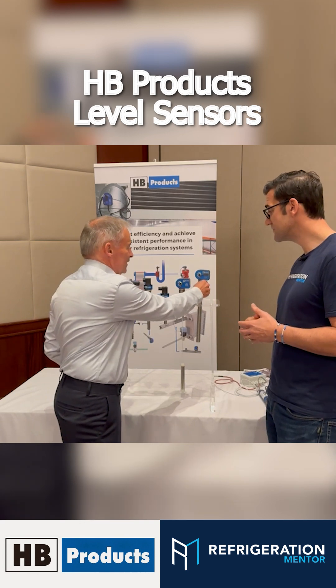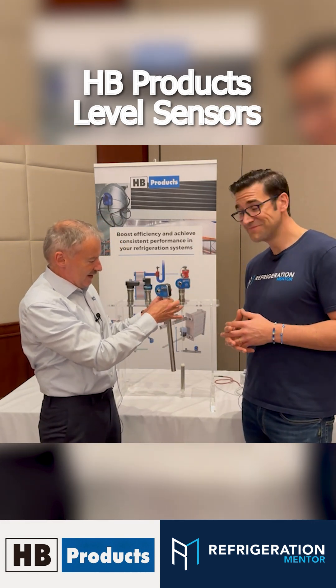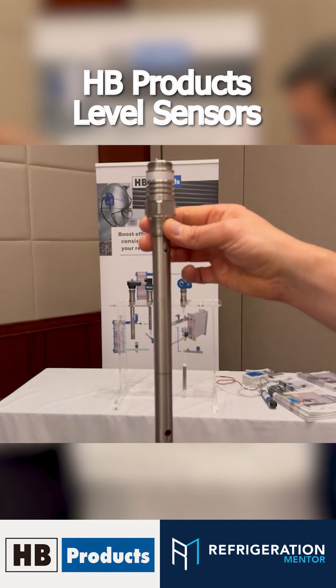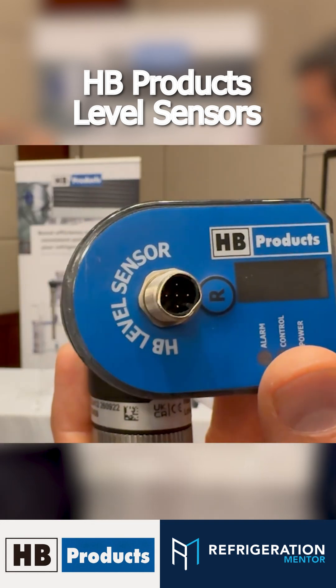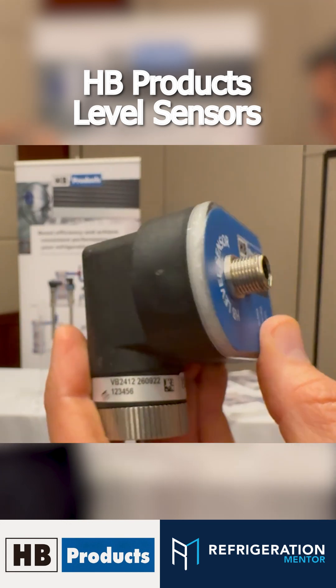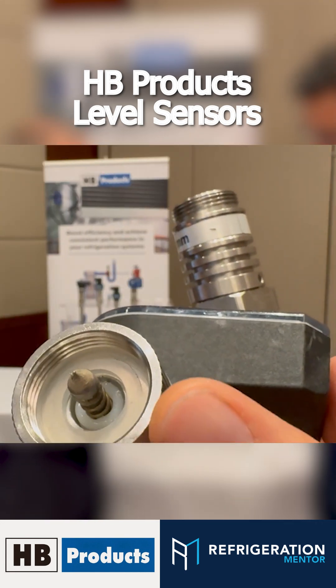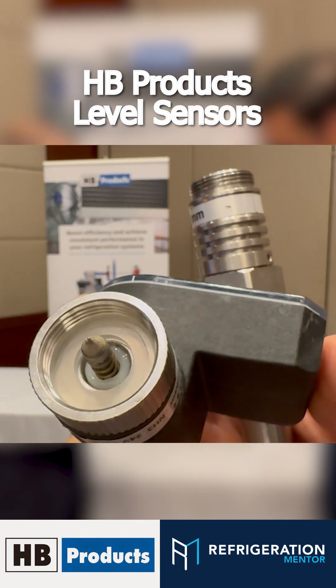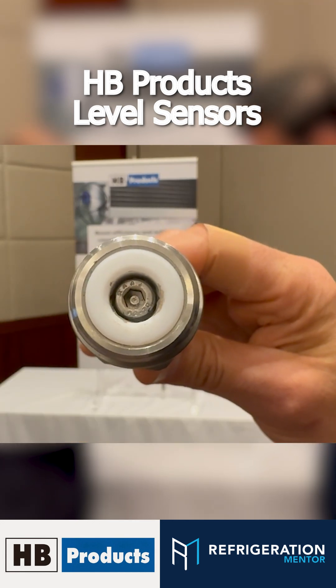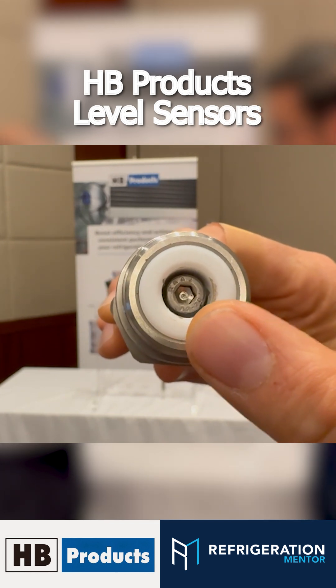Focus on this one which is a level sensor, level transmitter. It has a mechanical part which is sitting in the system. It can be under pressure and you can actually unscrew the electronic part — like this, you see. And so this little spring-activated thing is connected — goes right in there. And so this touches there and that does the connectivity.